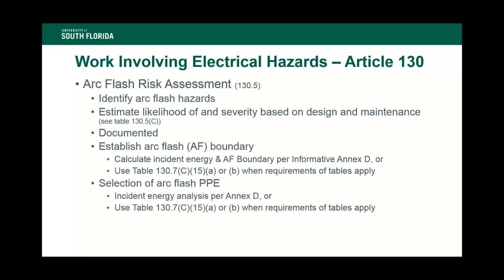Looking at arc flash risk assessment, it's basically to identify potential arc flash hazards. It estimates the likelihood and severity based on the design, maintenance, and actual physical condition of the equipment. And we can come up with this estimate of likelihood based again on another table in Article 130, Table 130.5(C). This risk assessment must also be documented, and we must establish an arc flash boundary.